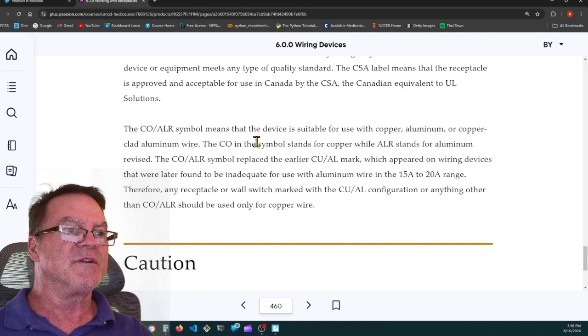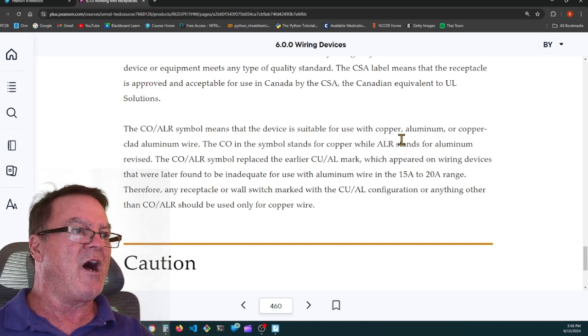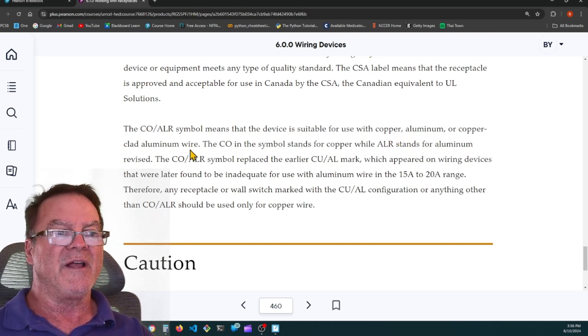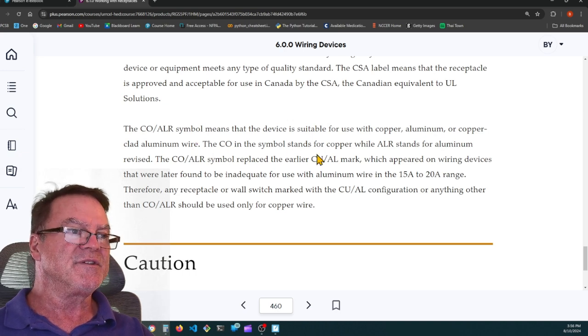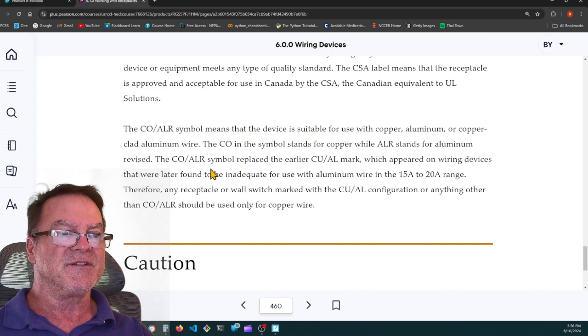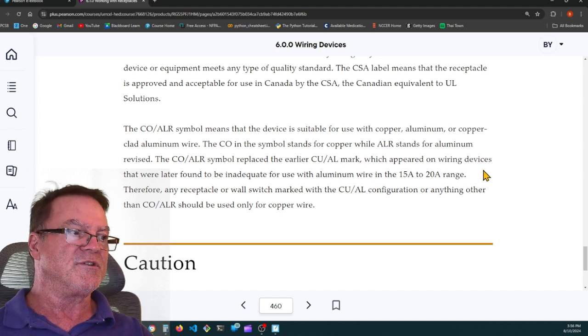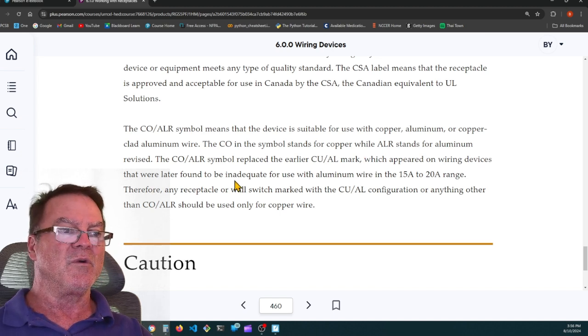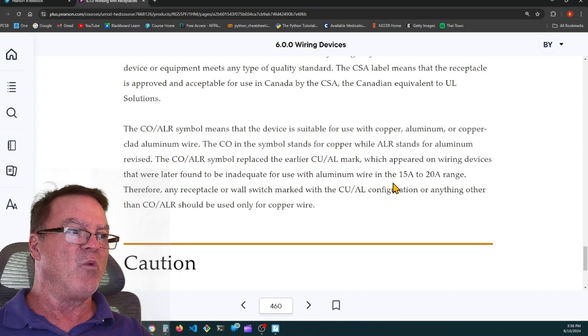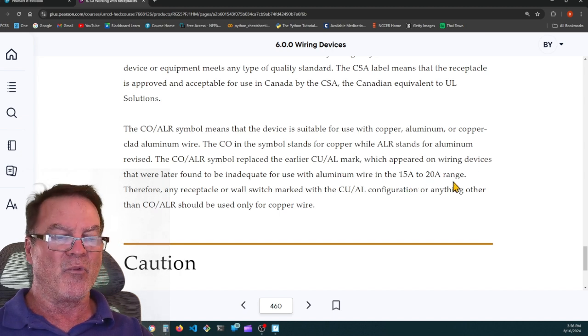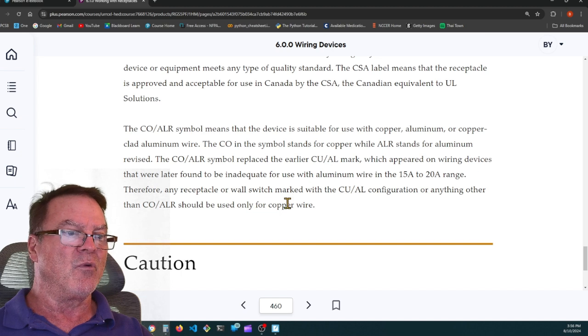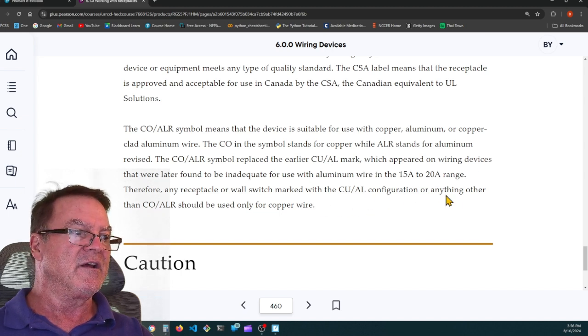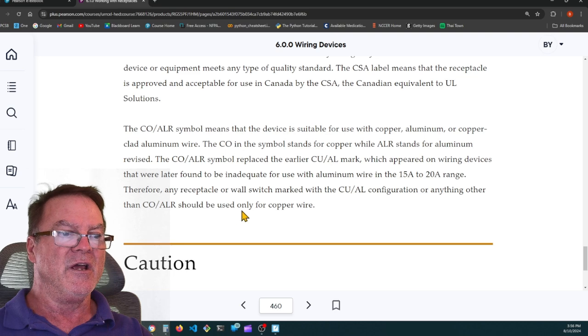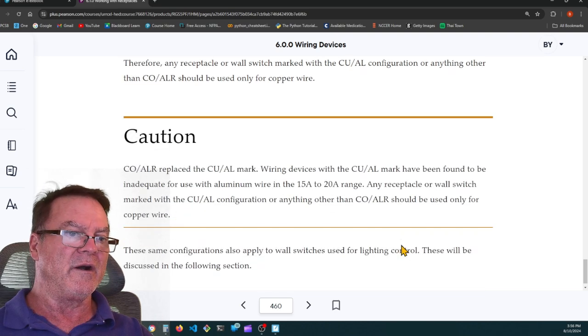The COALR symbol means that the device is suitable for use with copper, aluminum, or copper-clad aluminum wire. The CO in the symbol stands for copper, while ALR stands for aluminum revised. The COALR symbol replaced the earlier CUAL mark, which appeared on wiring devices that were later found to be inadequate for use with aluminum wire in the 15 amp to 20 amp range. Therefore, any receptacle or wall switch marked with CUAL configuration or anything other than COALR should be used only for copper wire.